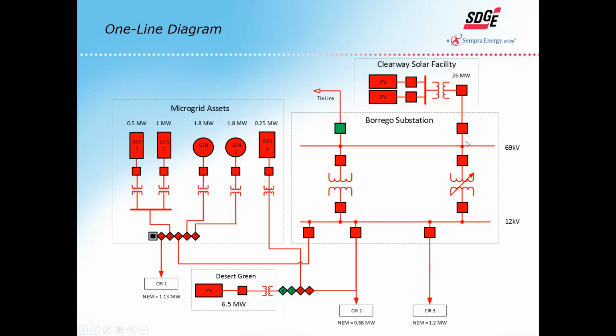We can energize everything connected to the 12 kV bus, which is all three customer circuits. We also have the ability to energize up to the 69 kV bus, where we're able to bring in this Clearway solar facility and keep the entire community of Borrego energized. So there's a lot of versatility with this microgrid, and our control systems really allow us to customize how we're going to operate.